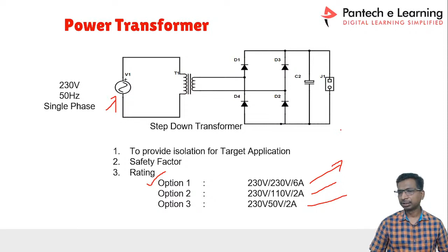This filter is going to give us a rectified and smooth DC bus voltage. Generally you can keep a 1000 microfarad electrolytic capacitor, based on the voltage range. If you are applying 230 voltage, you have to use a 400 voltage DC bus capacitor. Or if you are keeping a single capacitor, you can use 200 voltage with two capacitors, then you can go ahead.